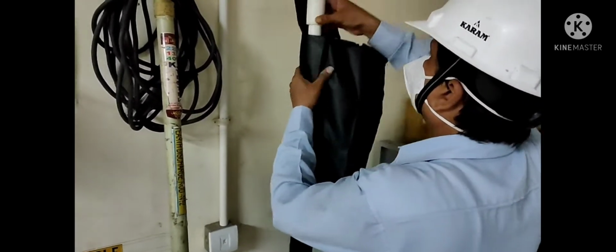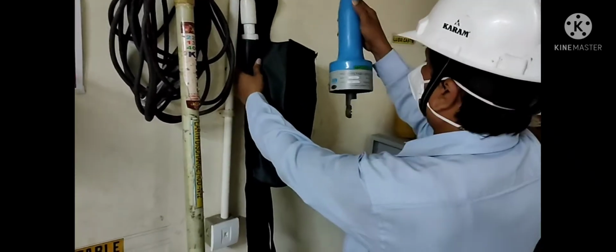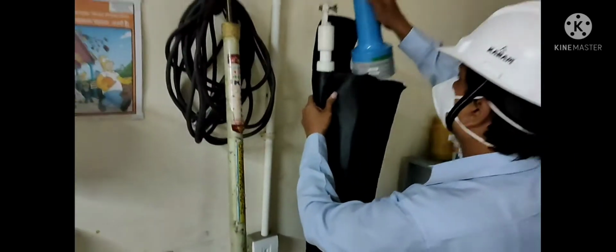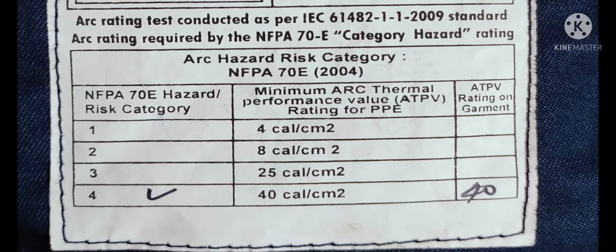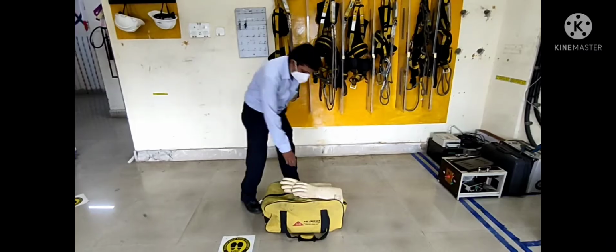After checking the live line detector and earthing rod, now we have to wear an arc flash suit. For normal operation, we recommend an 8 calorie per centimeter square arc flash suit, and for maintenance and isolation, it totally depends on the voltage rating and arc flash study. However, on the safe side, we recommend using a 40 calorie per centimeter square arc flash suit.